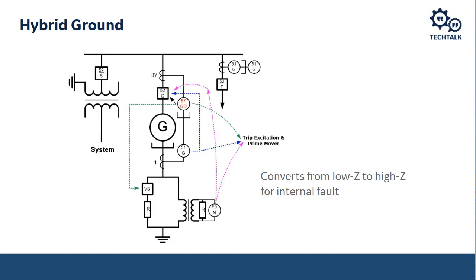our ground protection systems. However, once we've detected that ground fault, what we do is we very quickly open up that switch. So then we introduce the high impedance ground into the circuit. So it's a combination of low impedance and high impedance. As soon as we detect that ground fault, we do not subject the generator to that ground fault for long periods of time. We open it up and then we introduce the high impedance circuit, which then limits that ground fault current.